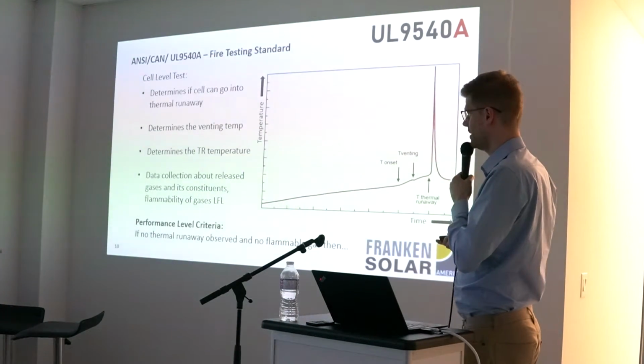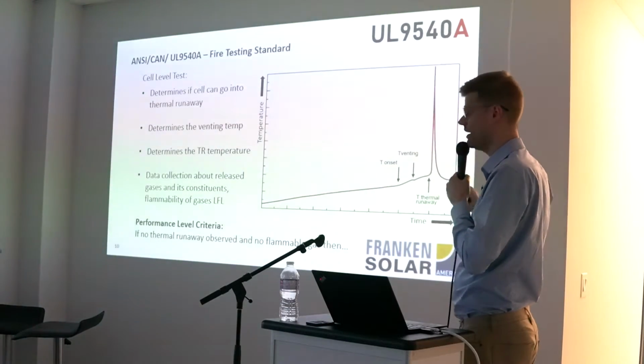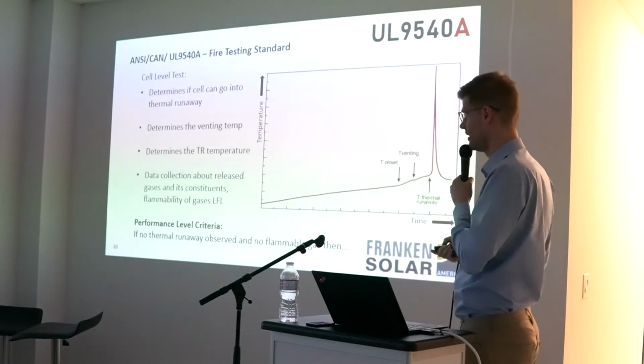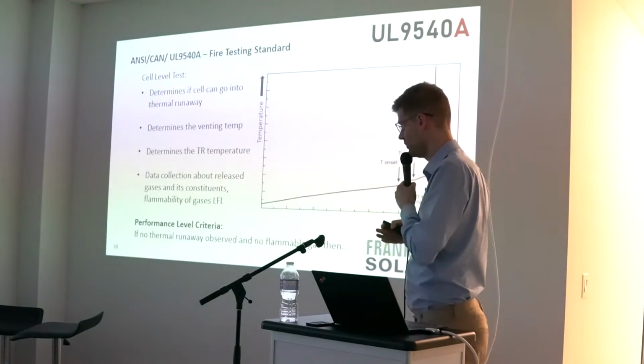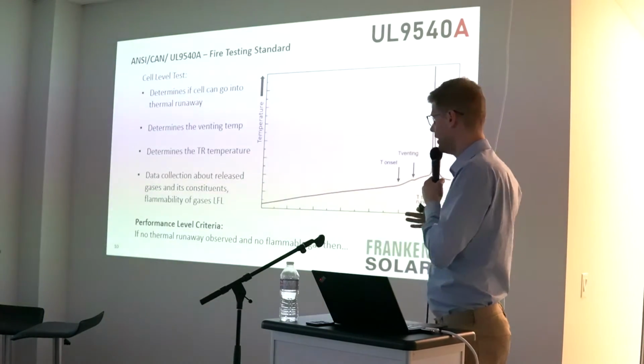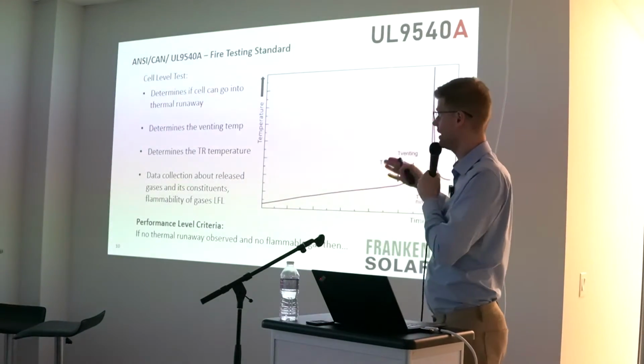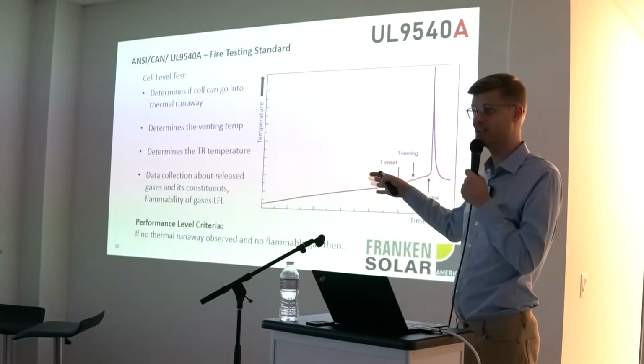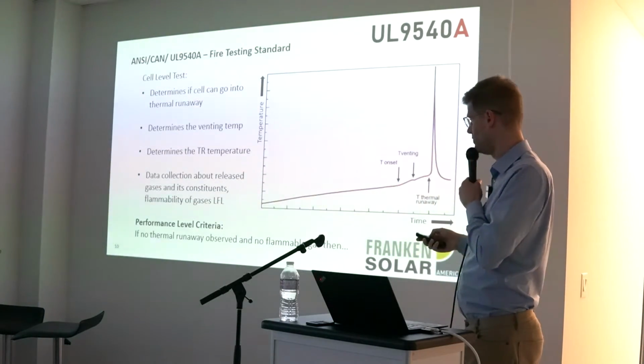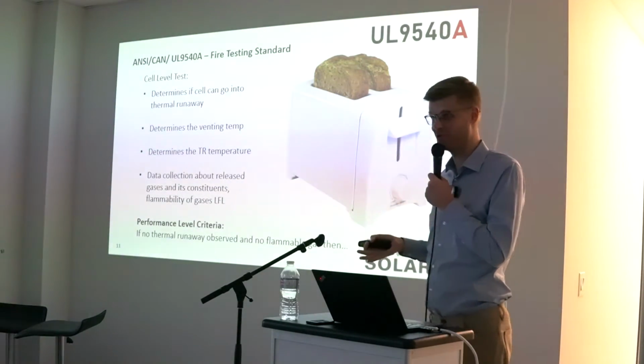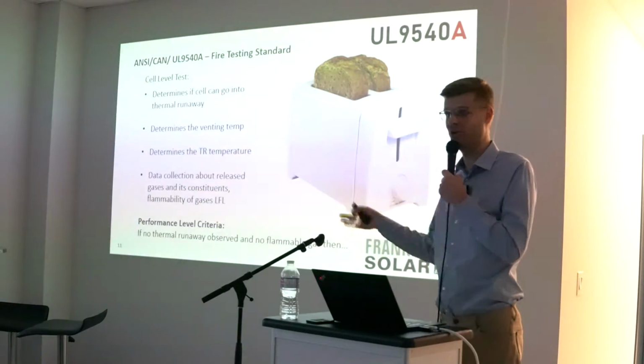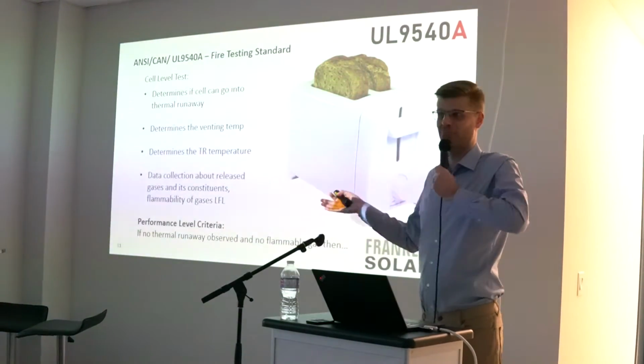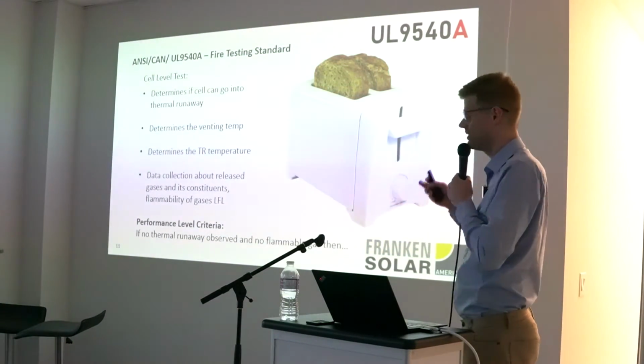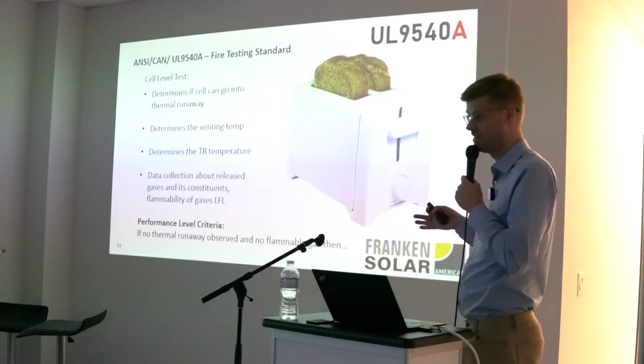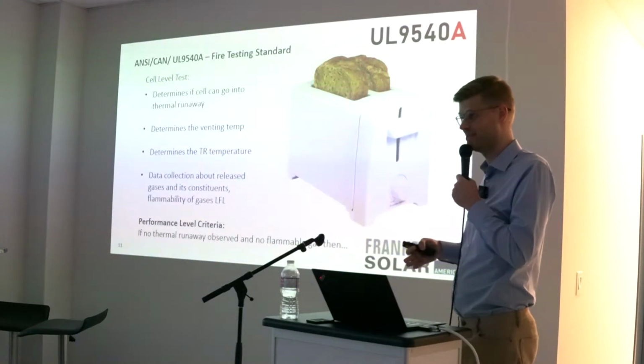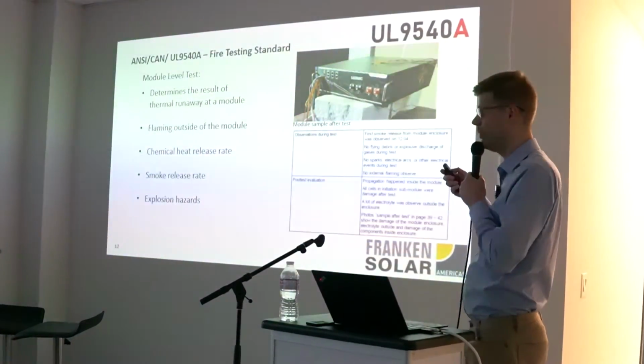The performance level criteria is: if you have a test unit, a cell, and the testing facility sees no thermal runaway and there are no flammable gases, then the cell would pass that test on the cell level. And then that system would be nothing else like a toaster in your household, because you can place that toaster anywhere you want, even in your bedroom, and it's like any other device you plug in. So this would be super safe, can be used anywhere. Unfortunately, as I mentioned, that cell doesn't exist, so we have to go to the module level.